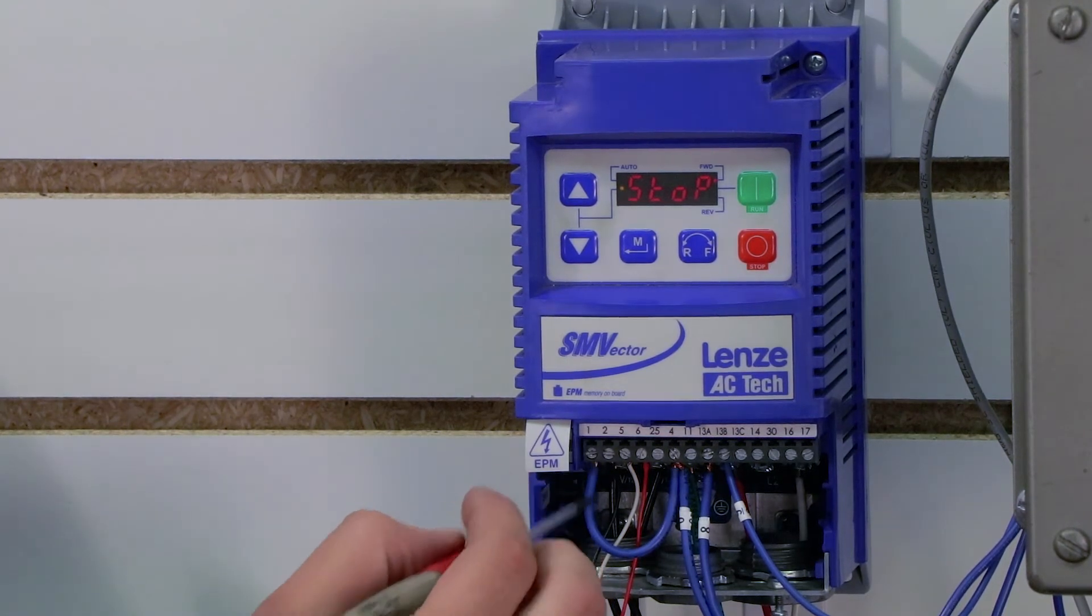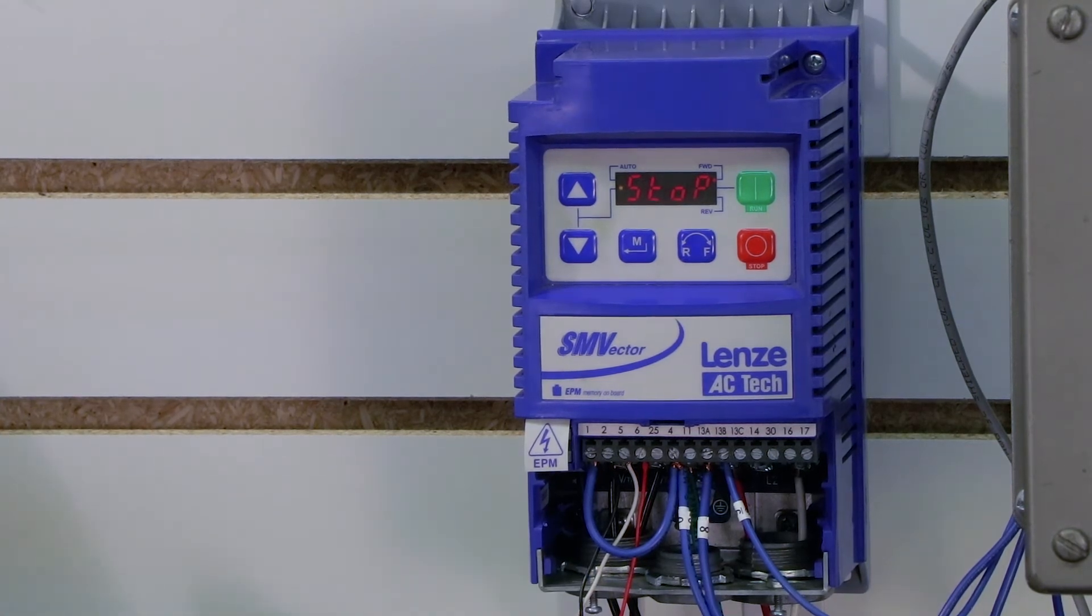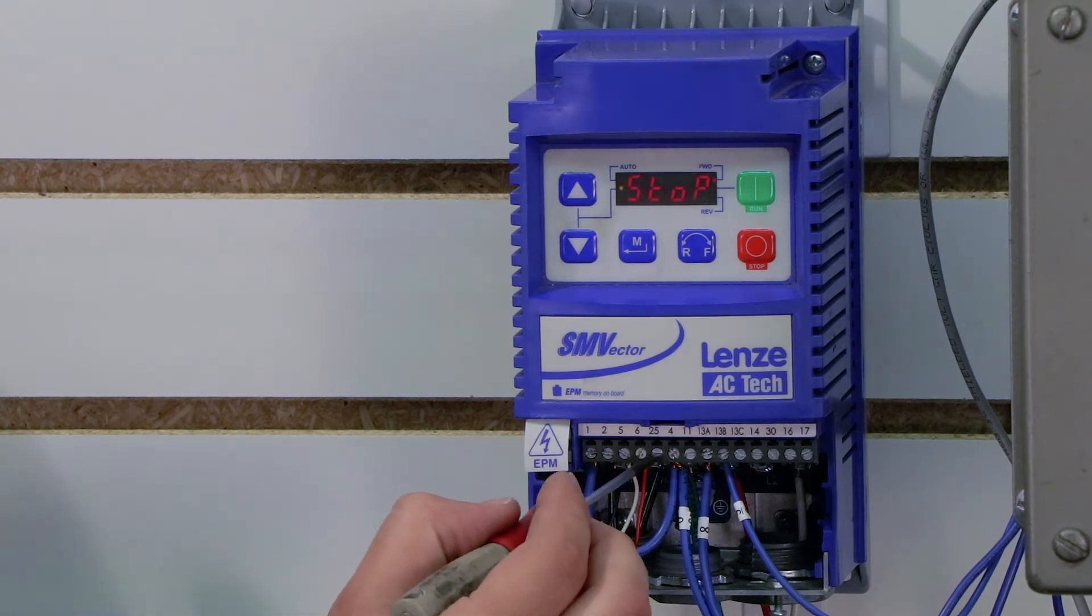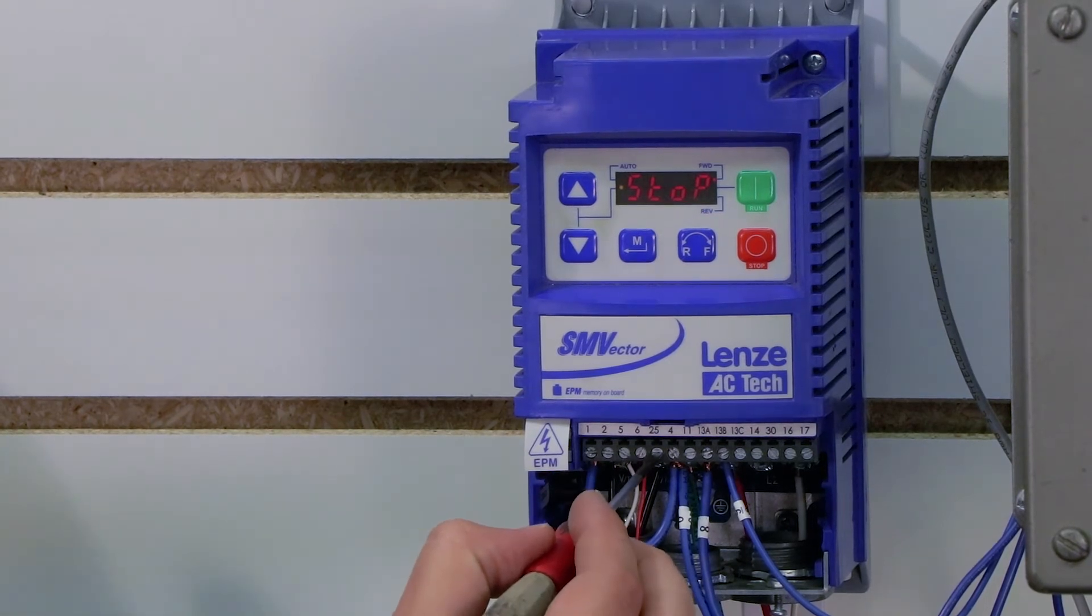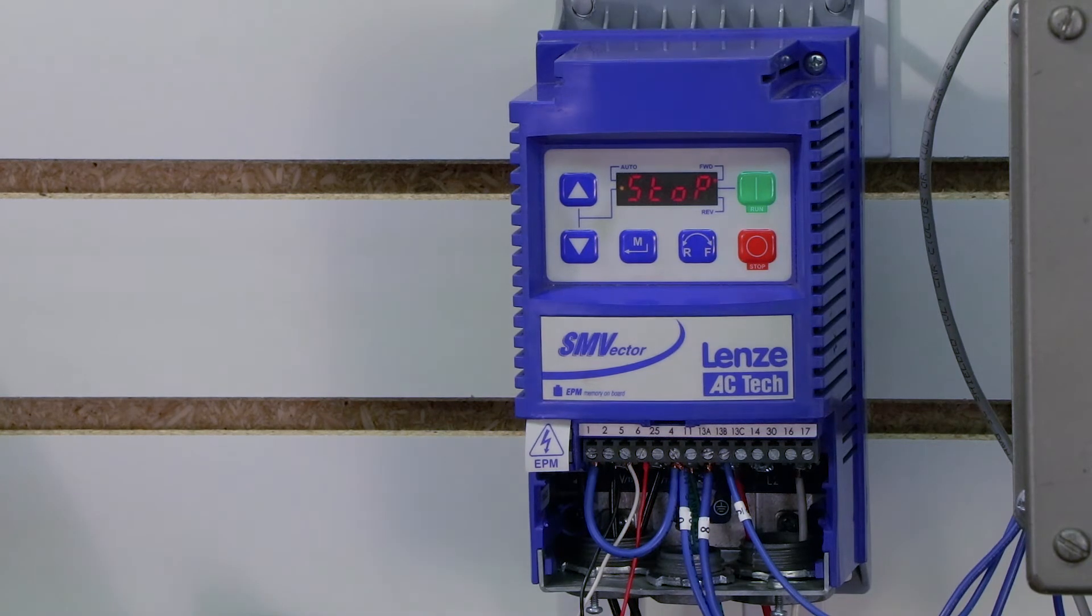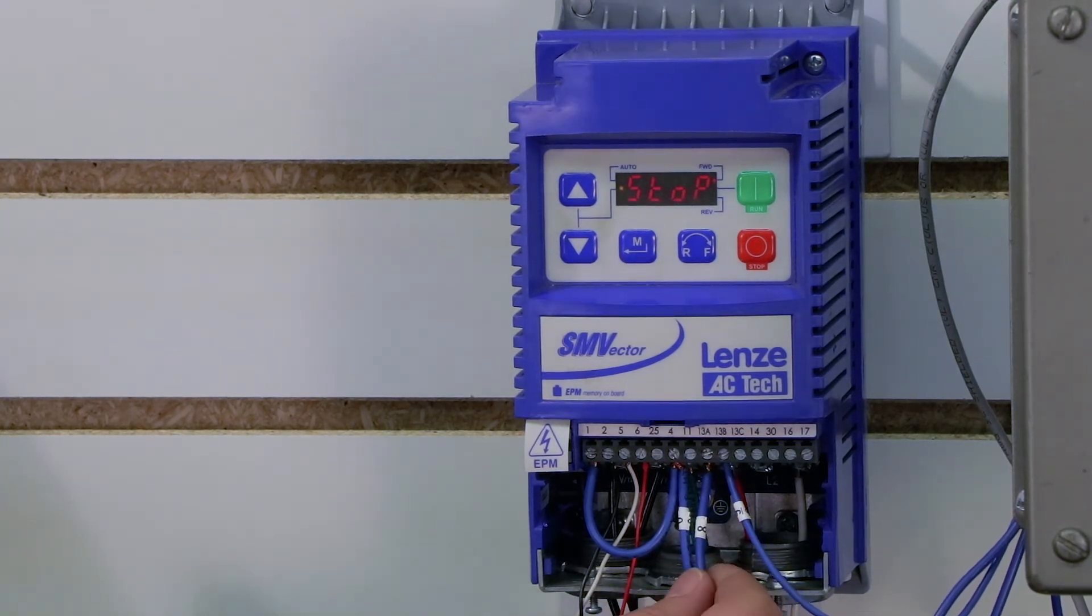And if you're using a 4 to 20 milliamp signal, then you're not going to use 2 and 5. You're actually going to use 2, which is again your common, and 25. 25 is going to be your 4 to 20 milliamp signal coming from your sensor. Now those are really the only wiring sections you need set up. So since I've got my input wired, I'm going to have to program that first. Let's start again in our manual.